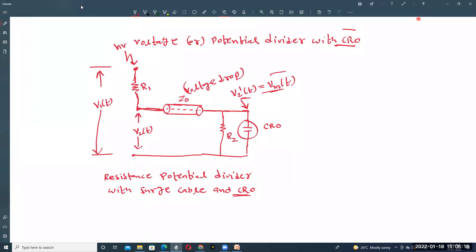In this simple basic resistance potential divider with surge cable, there are different types of errors in the measurement of high voltage. The first error is because the input resistance of the CRO, called R2, is not equal to the surge impedance of the cable, called Z-naught. Because of this mismatch, there is an error in the measurement of high voltage.